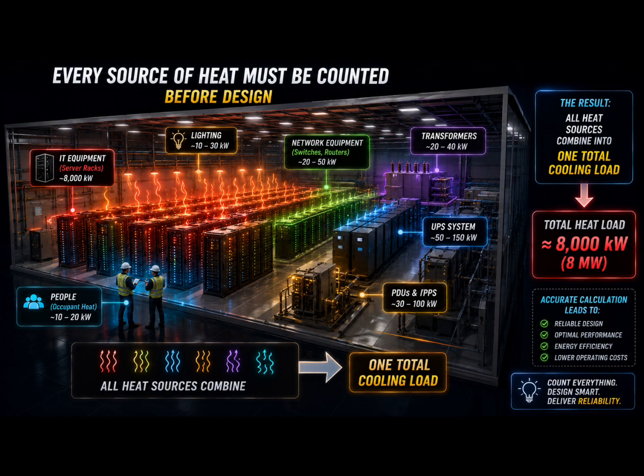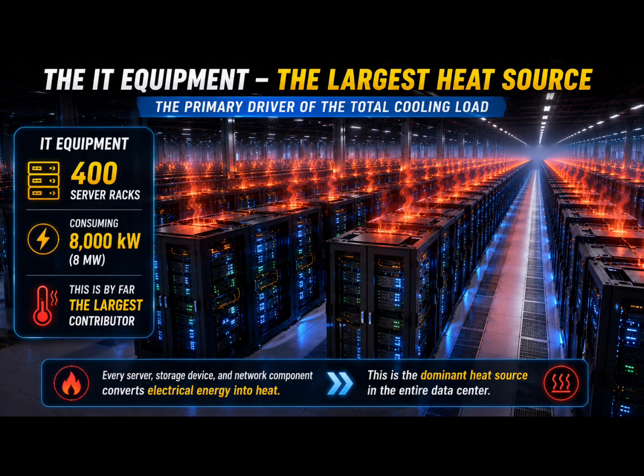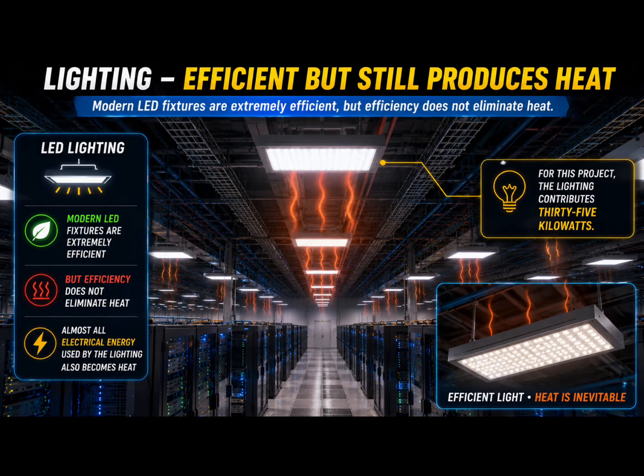Let's begin with the obvious one, the IT equipment. 400 racks, consuming 8,000 kilowatts. This is, by far, the largest contributor. Next, the lighting. Modern LED fixtures are extremely efficient, but efficiency does not eliminate heat. Eventually, almost all of the electrical energy used by the lighting also becomes heat. For this project, the lighting contributes 35 kilowatts.